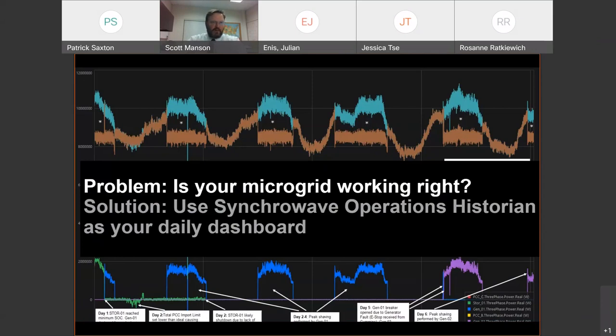Here's an example of a job we put into service. The top, the cyan color, is the total load on a job site. The brown is the imported power from the local utility. The difference is the power generated by batteries and by photovoltaics and by generators on that microgrid. Here you can see a demand shaving operation with real-time time synchronization. These data samples are not random. They are time synchronized to the millisecond or better in some cases. So we know exactly what these inverters are doing at any one moment.